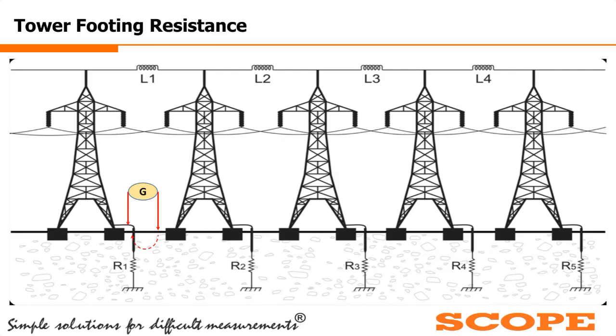With the help of this high frequency, let me just turn on the whiteboard. Whenever we inject the current, the path will be completed here, and since it is a high frequency signal, we will complete our measurement before this current travels to the multiple paths through the guard wire. So before the influence of these adjacent towers comes, we will have completed our measurement with the help of high frequency. That's why a high frequency source is required for tower footing resistance measurement.